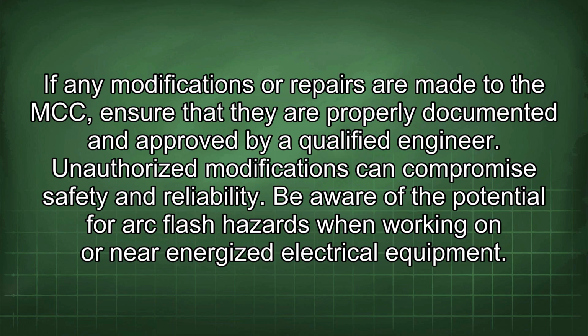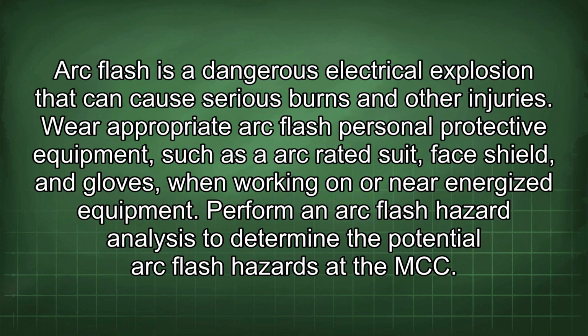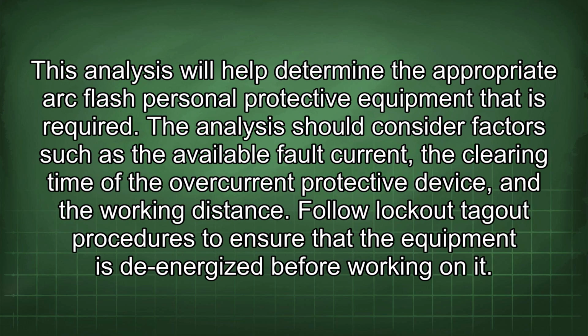Be aware of the potential for arc flash hazards when working on or near energized electrical equipment. Arc flash is a dangerous electrical explosion that can cause serious burns and other injuries. Wear appropriate arc flash personal protective equipment, such as an arc-rated suit, face shield, and gloves, when working on or near energized equipment. Perform an arc flash hazard analysis to determine the potential arc flash hazards at the MCC. This analysis will help determine the appropriate arc flash personal protective equipment that is required.